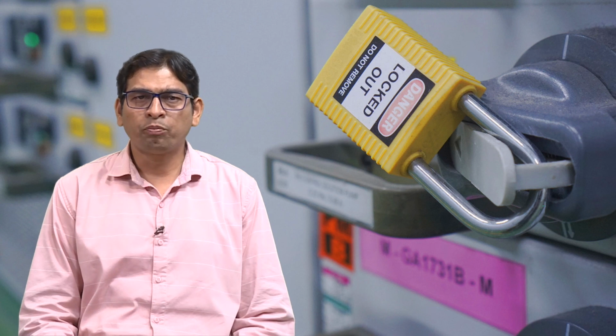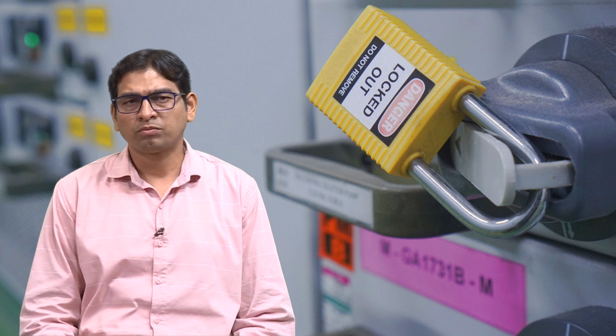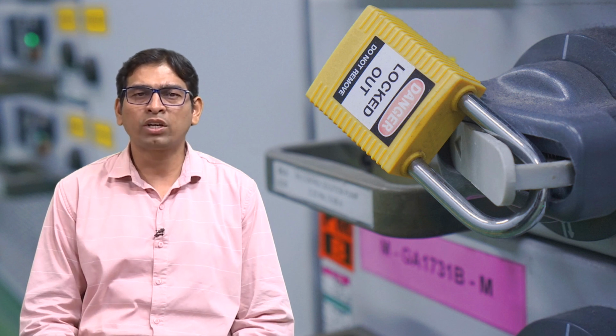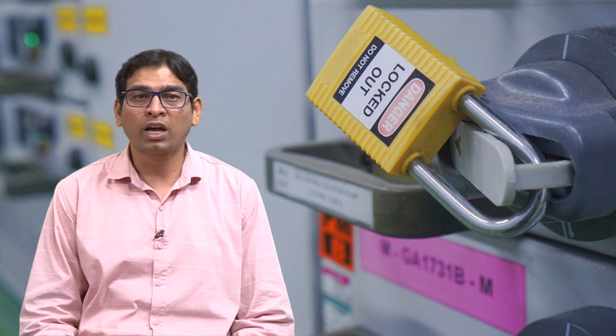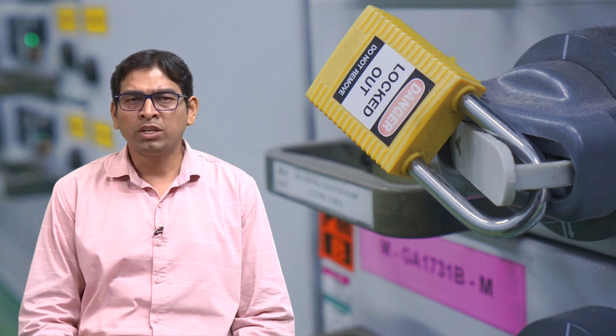Work can then be done on the equipment you are servicing. In some special situations, additional procedures must be followed when locking and tagging out a machine. One of the most important of these occurs if you have a personnel change during the time the equipment is being serviced. In this situation, it is important to maintain continuity of responsibility.